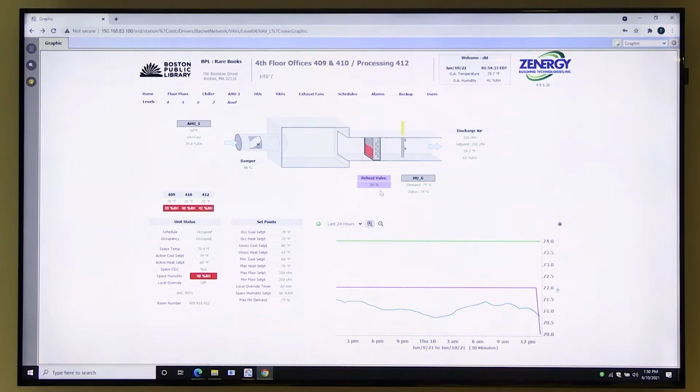The system isn't reliant on the communication necessarily to control each space or any given system. So if the communication were to go down for a small time or a large time, it's basically just going to remain in its last state based on its own sensors and everything. So it's going to continue to run, controlling that process for as long as the communication is down.